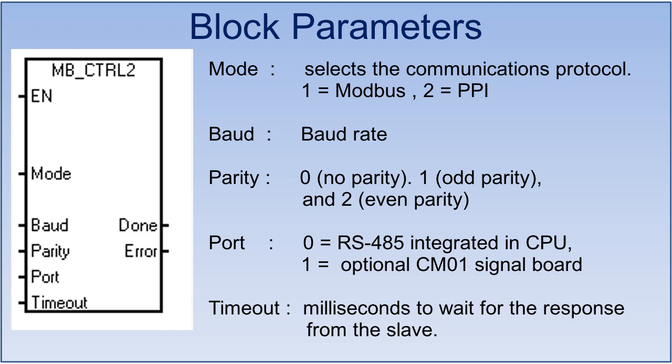Baud rate and parity will be as per the slave device configuration. If you are using onboard CPU port for communication then port will be 0, and if you are using external communication board CM-01 then port will be 1. Define the timeout in milliseconds to wait for the response from the slave device.